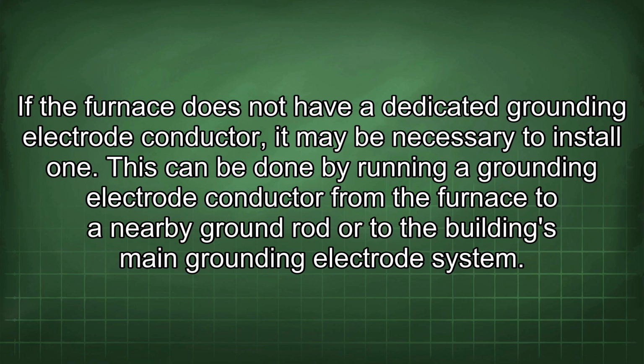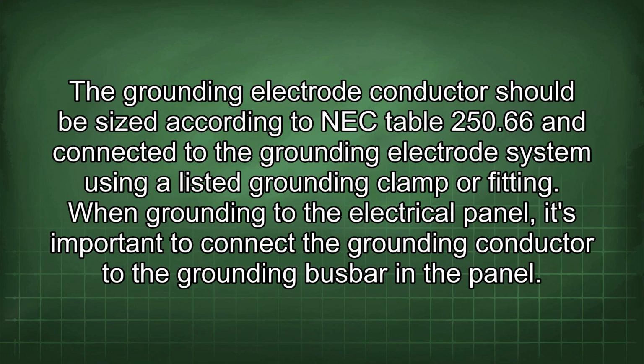This can be done by running a grounding electrode conductor from the furnace to a nearby ground rod or to the building's main grounding electrode system. The grounding electrode conductor should be sized according to NEC Table 250.66 and connected to the grounding electrode system using a listed grounding clamp or fitting.